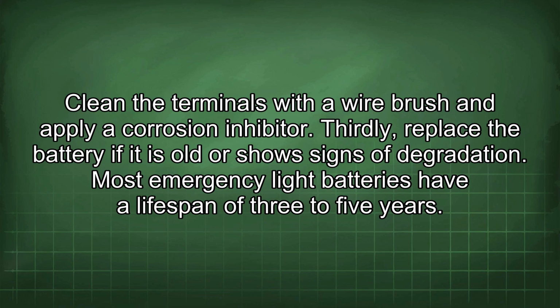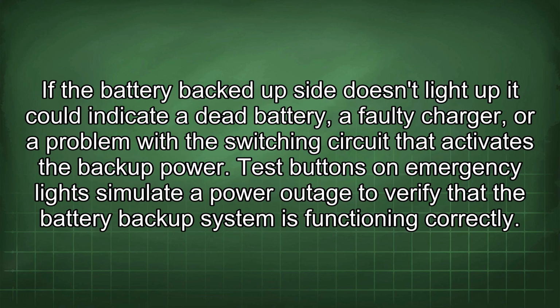Thirdly, replace the battery if it is old or shows signs of degradation. Most emergency light batteries have a lifespan of 3 to 5 years. If the battery backed up side doesn't light up, it could indicate a dead battery, a faulty charger, or a problem with the switching circuit that activates the backup power.